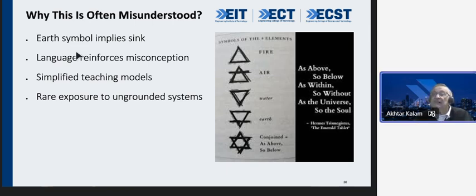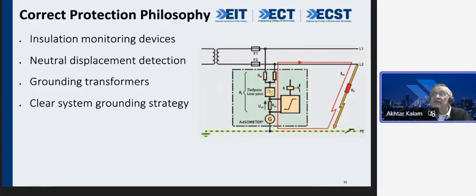So now the correct protection philosophy should be that we have monitoring devices on the insulation. We have detection of the neutral displacement. We have grounding transformers, and we have clear grounding strategies. If you have that, you can't go wrong. Protection must match the grounding philosophy, or it will not work. In this case, it did not match, and therefore it did not work.